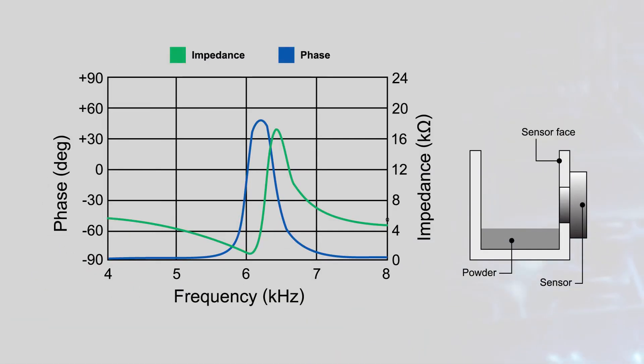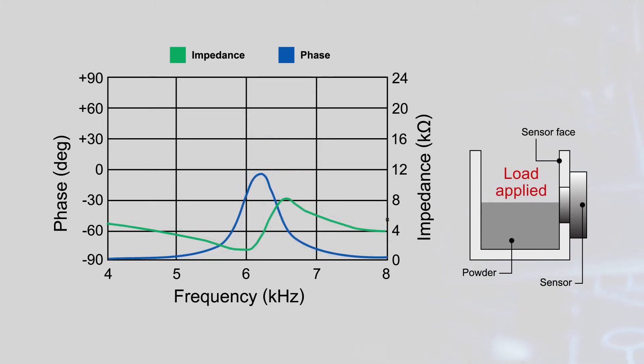As powder contacts the sensor face, it changes the sensor's characteristic impedance versus frequency, becoming more capacitive as the load on the face increases. The powder level can then be determined by checking the phase of the sensor's impedance. This sensing technique also allows the sensor to detect both magnetic and non-magnetic powders.